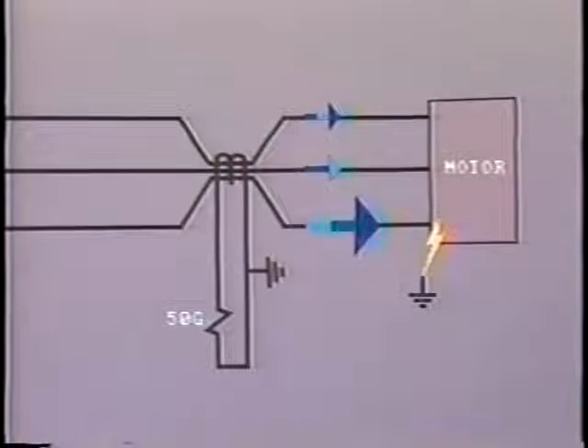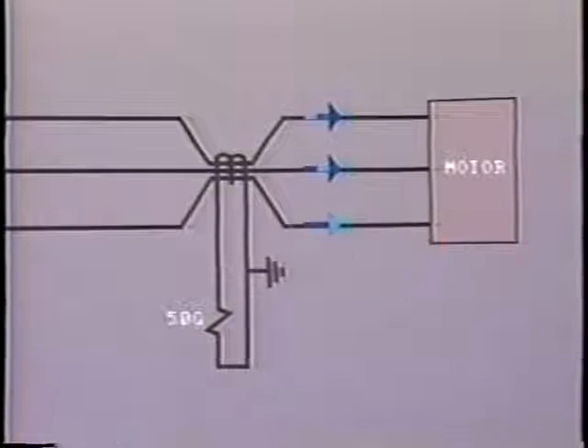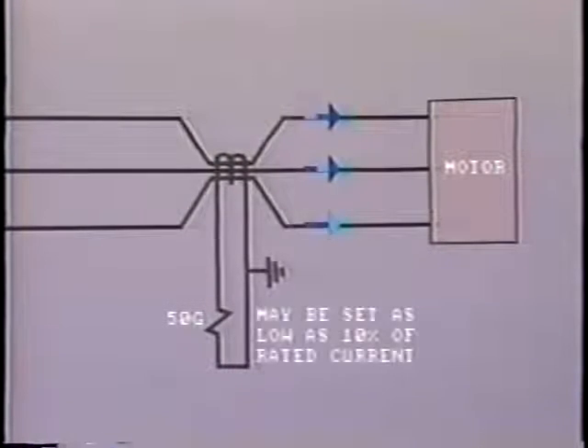However, if a ground fault occurs on the stator winding, there will be significant out of balance, and sufficient residual current will flow in the CT secondary to operate the 50G relay. We have seen this type of ground protection quite often before in this program. It is very sensitive and may be set as low as 10% of rated current.